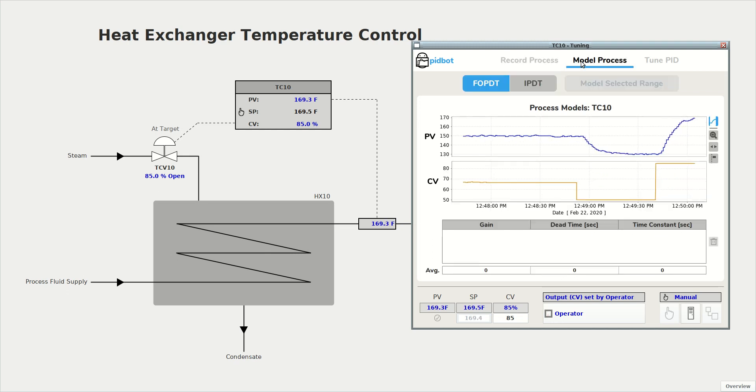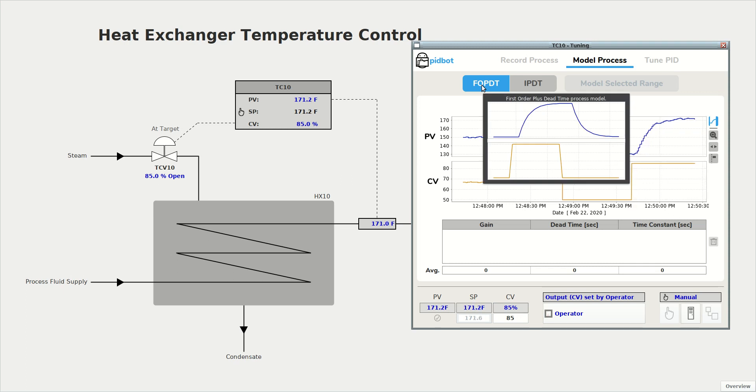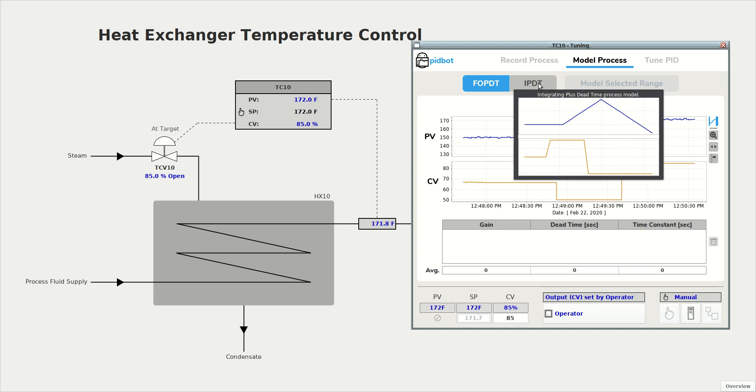We'll do that on the second tab. You want to select the type of process model that you're going to use. In our case, we're going to use the first order plus dead time model. That's always the case or almost always the case for temperature control loops. If you mouse over these buttons, it shows you what a typical response would look like for the first order process. When you step the CV, you eventually reach a new steady state, whereas the integrating process does not reach a steady state. It would continue increasing or decreasing forever.